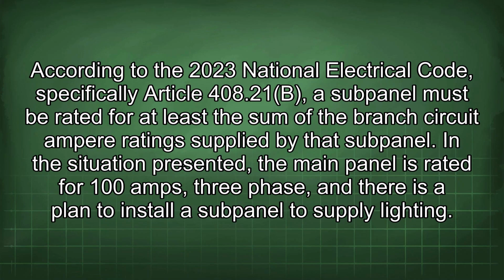According to the 2023 National Electrical Code, specifically Article 408.21(B), a subpanel must be rated for at least the sum of the branch circuit ampere ratings supplied by that subpanel. In a situation presented, the main panel is rated for 100 amps, 3-phase, and there is a plan to install a subpanel to supply lighting.